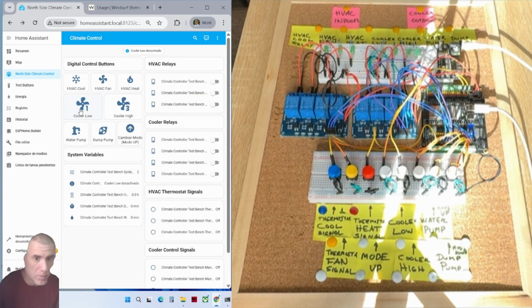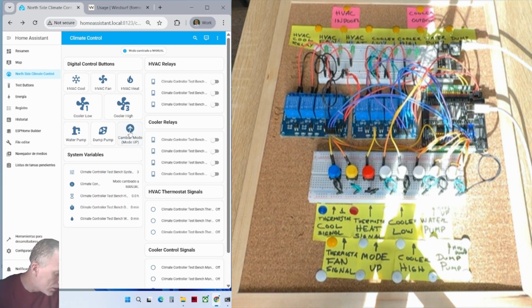Now we will test the next mode, manual mode, in which we can override each part of the cooler. We can override the blower in cooler low signal, only this one, and we can turn it off. We can turn on the cooler high, only the blower, and turn it off. We can override the water pump, and we can override the dump pump.